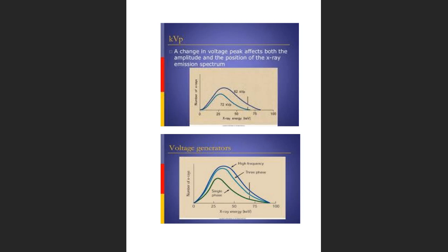Say all my energies are compacted in a 25 to 75 kVp range. That would be a harder beam because I got rid of the lower ones. So this beam would be more penetrable. If I make it a more penetrable beam, then I need more protective barrier to absorb those X-rays because the overall X-ray energies are higher. Does that make sense to you?